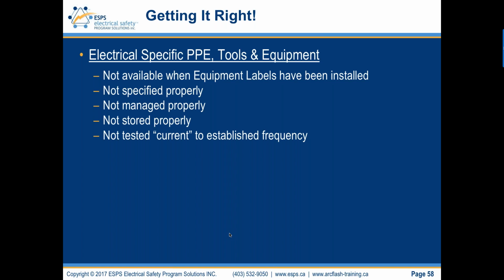For PPE, you need to manage test frequencies for rubber insulating gloves to six months as per ASTM standards, as well as hot sticks and temporary protective grounds. They aren't documented with a specific test frequency under ASTM standards. But for non-utility, I recommend 24 months for hot sticks and 36 months for temporary protective grounds. So again, you've got to manage all these nuts and bolts. In fact, PPE needs its own program within your electrical safety program. I call it a program within a program.